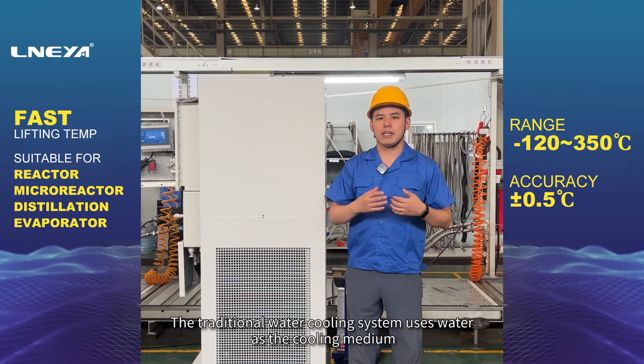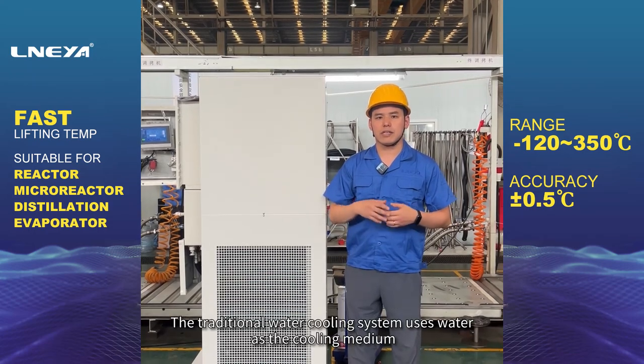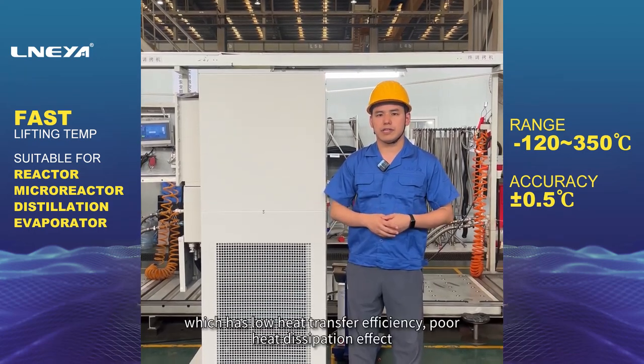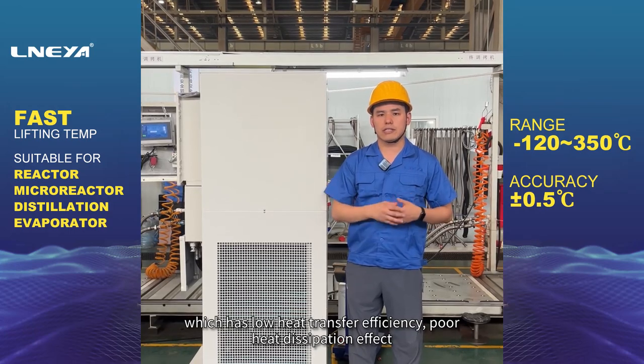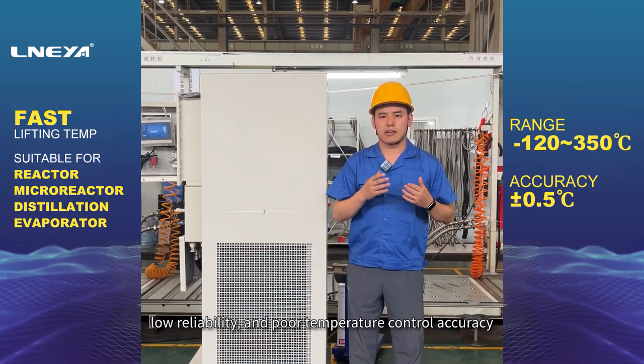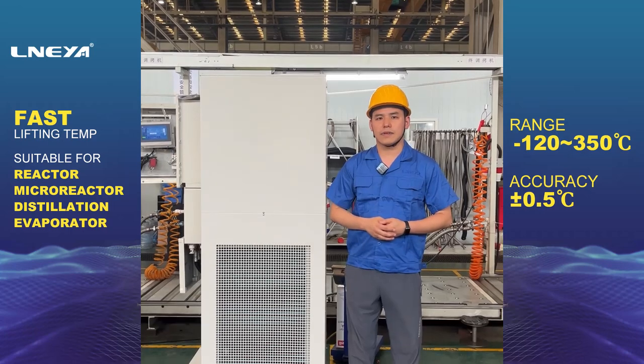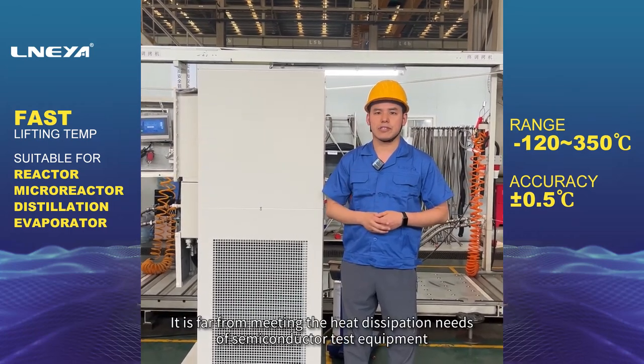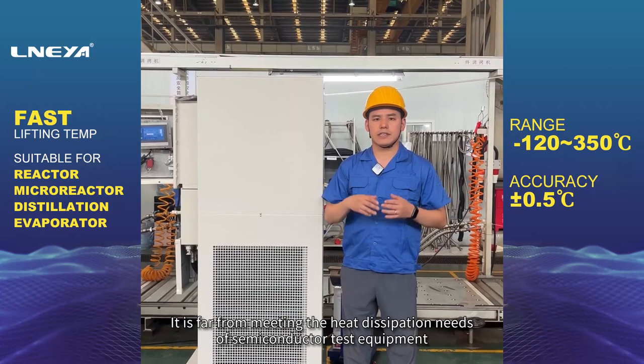The traditional water cooling system uses water as the cooling medium, which has low heat transfer efficiency, poor heat dissipation effect, low reliability, and poor temperature control accuracy. It is far from meeting the heat dissipation needs of semiconductor test equipment.